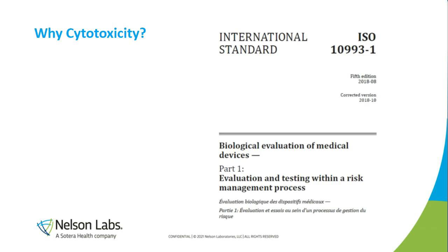Every medical device that has contact with the patient or the medical personnel has to go through a biocompatibility assessment to make sure that it's safe to be used. A biocompatibility assessment is performed per ISO 10993-1, which is the framework to do this assessment. And as you can imagine, the specific risks associated with a given medical device are tightly tied to its use, its intended type of contact, and duration of contact.